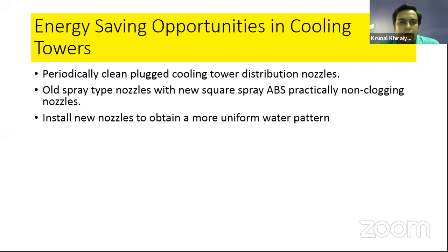Now, the next component, that is water distribution systems. Periodically clean the cooling water distribution nozzles. Meaning as COCs increase, your nozzles get clogged, so after some time you need to clean them so that water distribution and atomizing processes happen at a very fine rate. The second opportunity is replacing old spray type nozzles with new spray type nozzles, which are now available in the market. You need to install new nozzles as and when required to get a uniform flow pattern of water distribution.